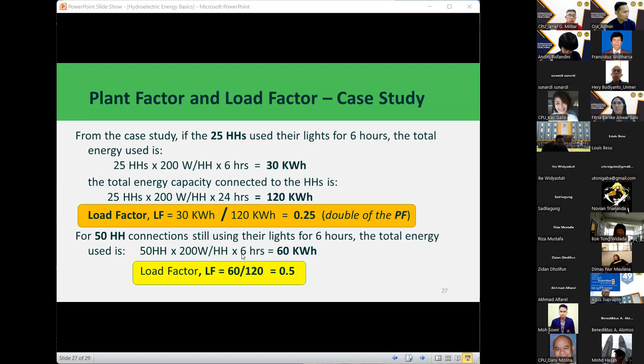So for economic considerations, the more the plant factor or capacity factor approaches 1, the better. So the designer should aim for a higher plant factor or higher load factor. So the key design rule for microhydro therefore is: design for the highest possible plant and load factors.